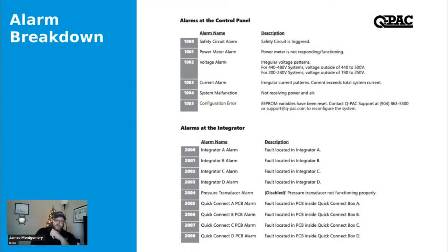So that means that device can't tell you the status of your fans. And that's the same for 2000 through 2003. I've got a list of things that need to be checked, and going back and verifying the wiring between the control panel and the quick connect box is the first one on that list. It's always ring out your wires, check for shorts, check for grounds, make sure they're not shorted to each other, make sure you got your colors correctly.